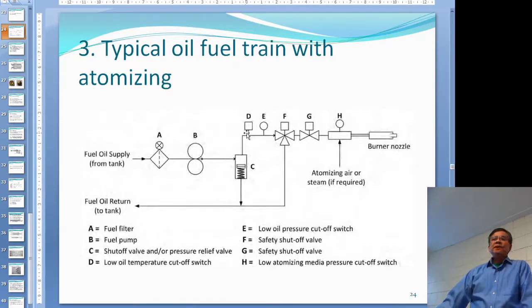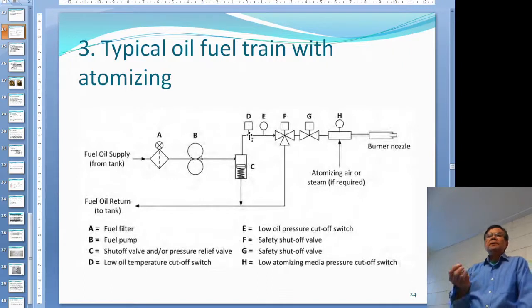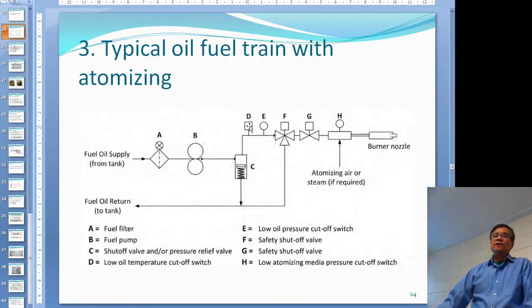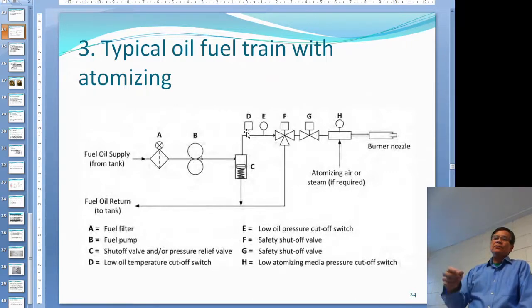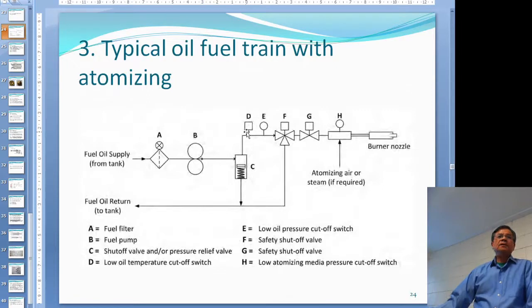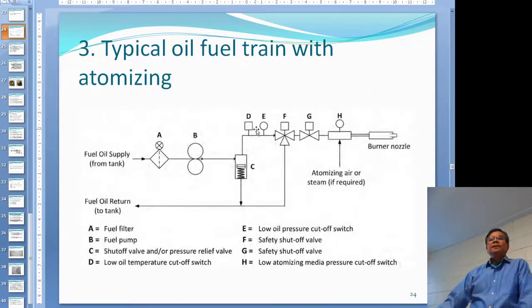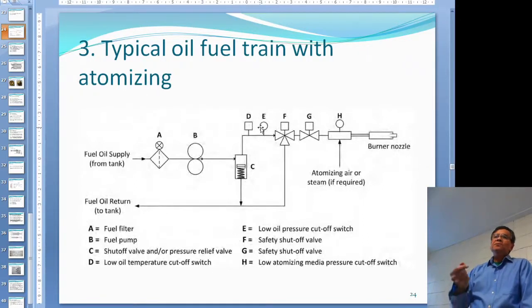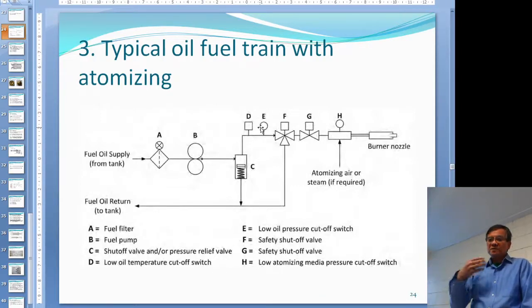Then you go through a couple of safety switches. D is a low oil temperature cutout — if the oil temperature is too low to burn, it cuts off. E is the low oil pressure cutout, which will always be there. If you don't have enough oil pressure to supply the burner, you cannot sustain burning, so it shuts off.